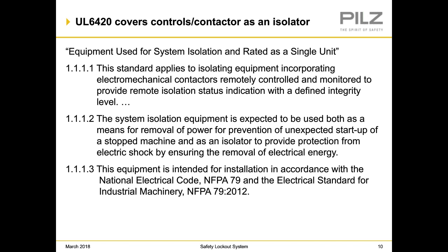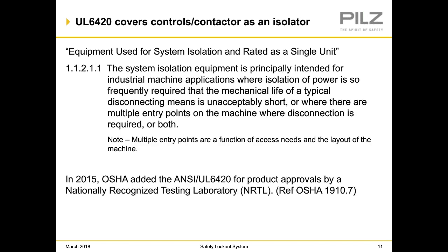This equipment is intended for installation in accordance with the National Electric Code, NFPA 79, and the Electrical Standard for Industrial Machinery, NFPA 79-2012. The system isolation equipment is principally intended for industrial machine applications where the isolation of power is so frequently required that the mechanical life of a typical disconnecting means, as we saw in the typical operations of a disconnect switch, is unacceptably short, or where there are multiple entry points on a machine where disconnection is required, or both of the above. In 2015, OSHA added the ANSI UL 6420 for product approvals by a nationally recognized testing laboratory, or NRTL, as it's sometimes referred to. You can reference OSHA 1910.7 for that.